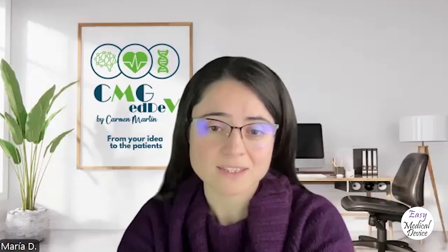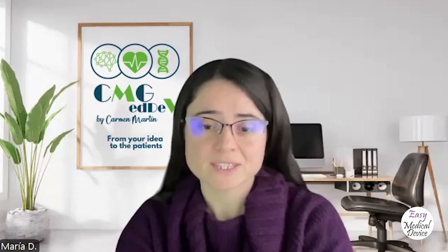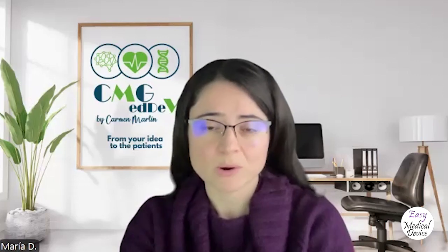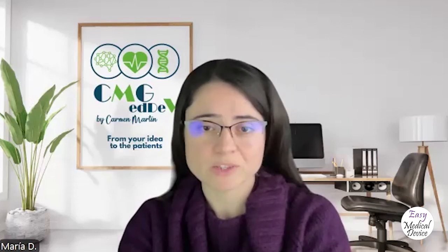So, one thing that is important: if I have made a change that is non-significant, but it has not been mentioned in the PCCP, does it mean that I should anyway communicate that change to the FDA? Well, you should refer to the guidelines explaining what type of changes you need to notify. If it is a change that you should notify and you have included it in your PCCP, no problem. You have it covered. You need to follow your procedure and it's fine.